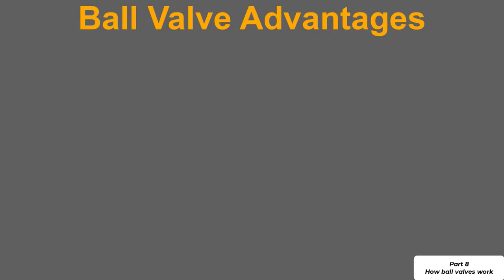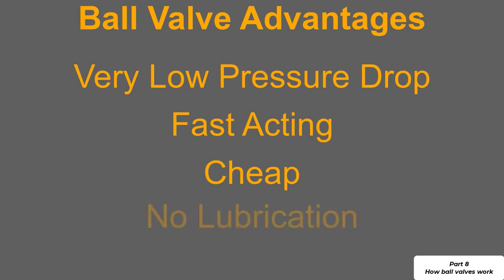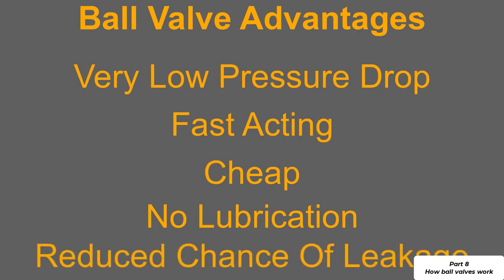The ball valve itself because it can open up to allow complete flow through the valve has a very low pressure drop. That means the flow is almost unrestricted through the valve. That is one big advantage. Another advantage is that the valve can be actuated very quickly, it only requires a quarter of a turn. The ball valve itself is relatively cheap and has low maintenance costs. It requires no lubrication and one of the final advantages is that the ball seals very well against the seat and this reduces the likelihood of leakage.